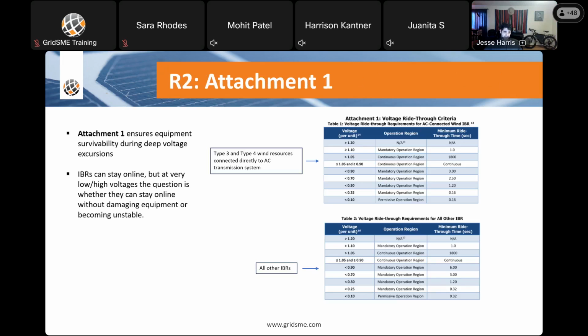So here's attachment 1. Essentially, it ensures equipment survivability during deep voltage excursions. If you look over here, you have this continuous region right here. This is that kind of normal operation region, and then you have your mandatory, and then at that real low voltage, you have your permissive. Note that there are 2 tables here. Table 1 is for type 3 and type 4 wind resources, and then table 2 is for all other IBRs.